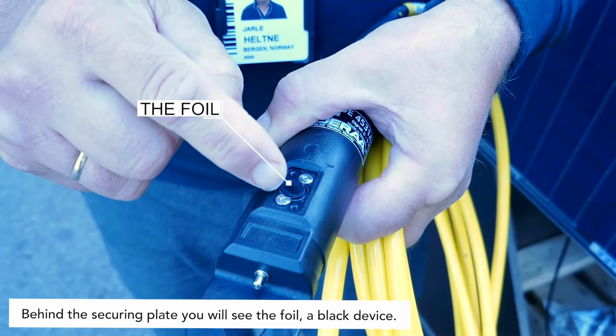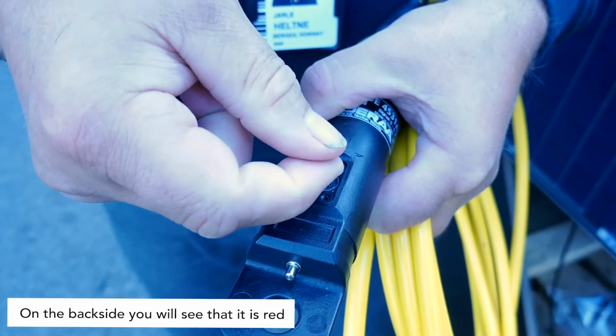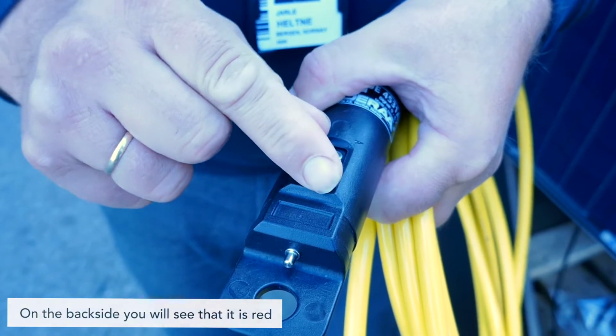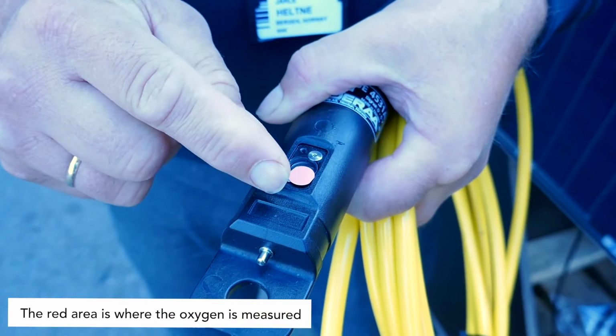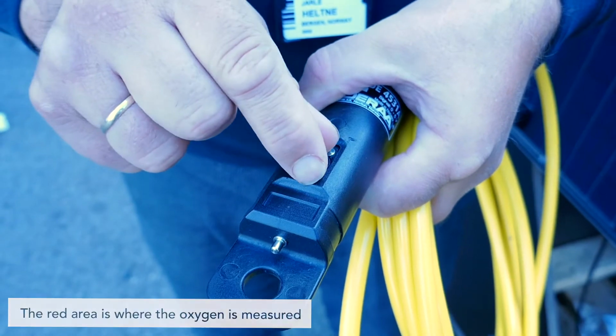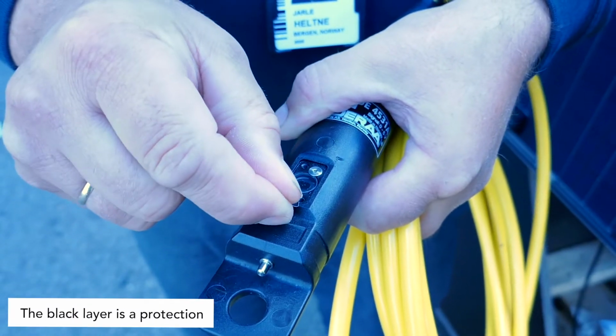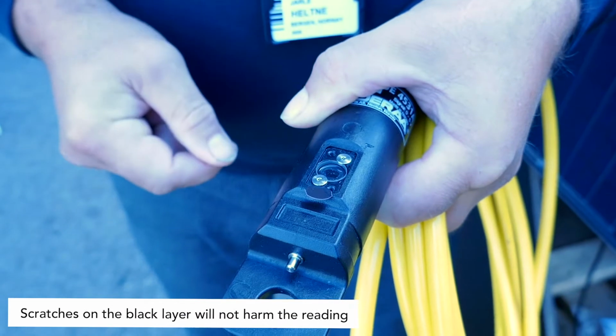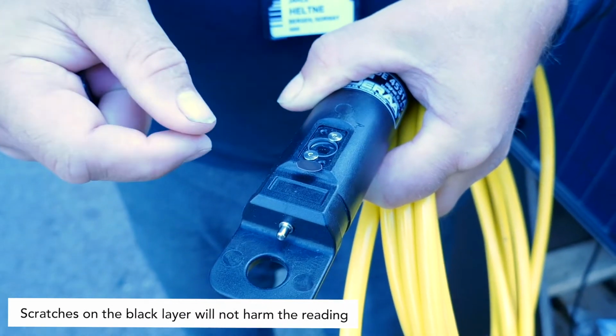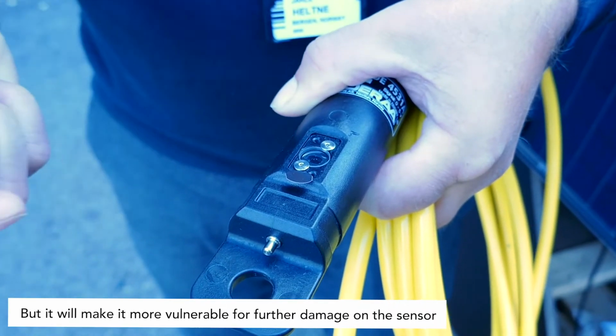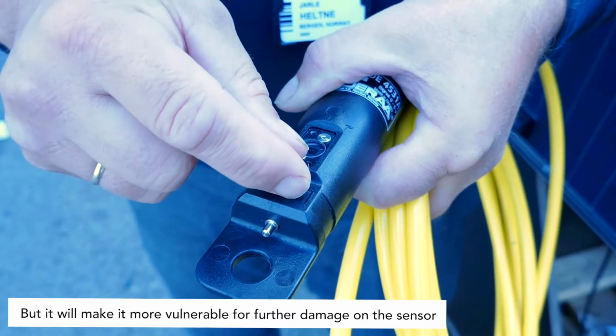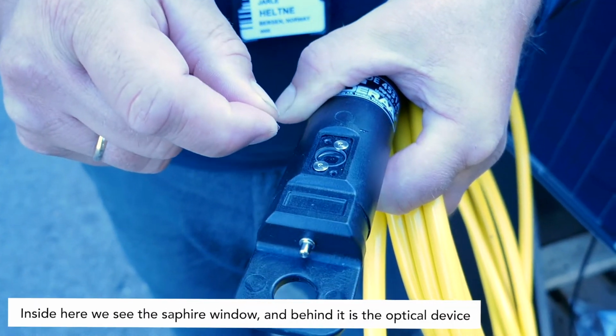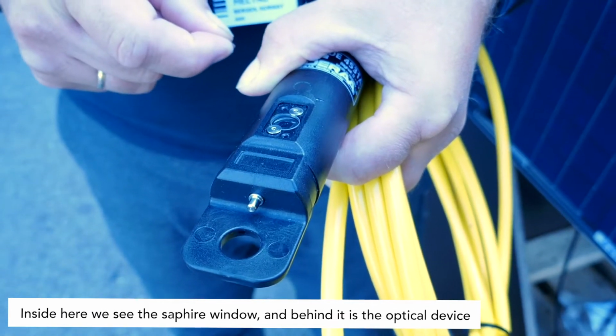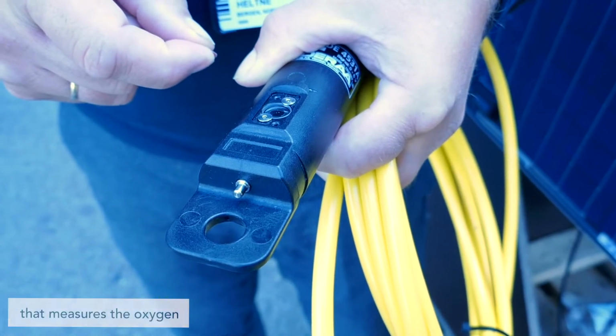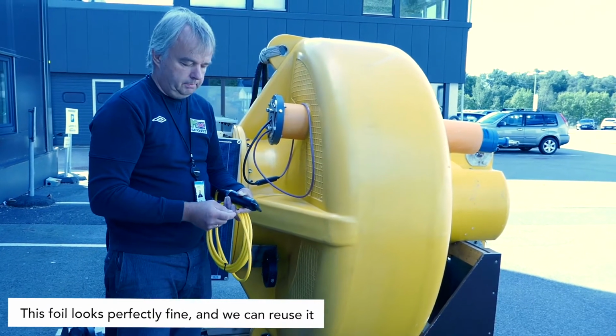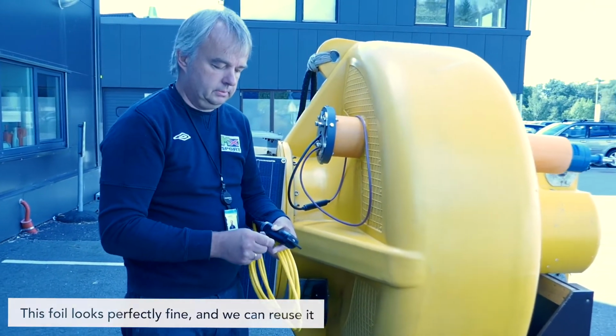The foil is this black device. On the back side you will see that it is red. The red is the area we're measuring the oxygen, and the black layer is just protection. So if there is some scratches in the black layer, that won't harm the reading, but it's then more vulnerable for further damage on the sensor. Inside here we see the sapphire window, and behind there is the optical device that's measuring the oxygen. When we look at this foil, it's perfectly fine, so I can reuse this one.